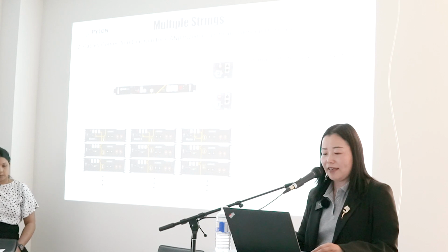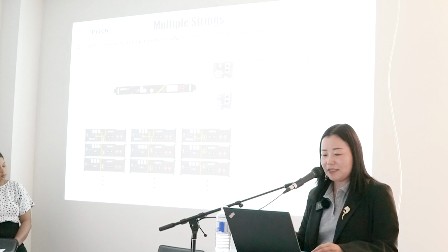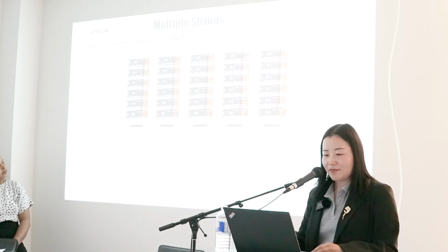Cable 3, the CAN of the first master battery connects to the LV hub, port 1 to 7 freely. Cable 4, on the LV hub, the CAN in connects to port 0. Cable 5, LV hub CAN out port connects to the inverter CAN port. So here is the multiple strings cable connection diagram for CAN.